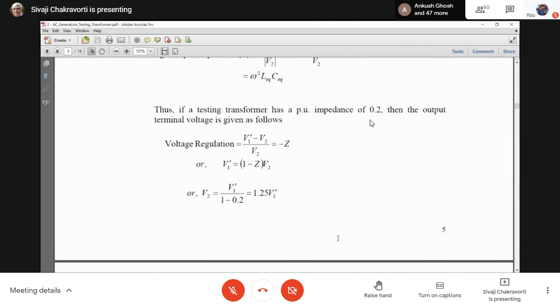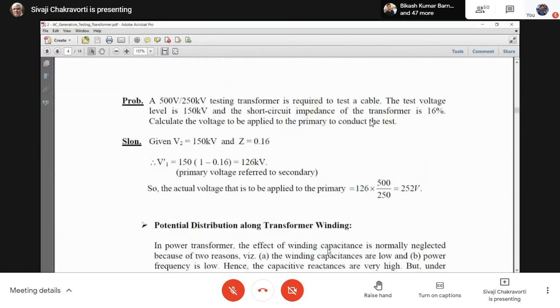So that's what I was trying to tell you: V2 is the terminal voltage. If I want to apply 28 kV at the terminal of the equipment under test, I cannot have a transformer voltage of 28 kV. It should be much lower, because there is a voltage regulation involved. So there is a problem. Just read the problem statement, then I will explain. A 500 volt by 250 kV testing transformer is required to test a cable. This is an important point: to test a cable.